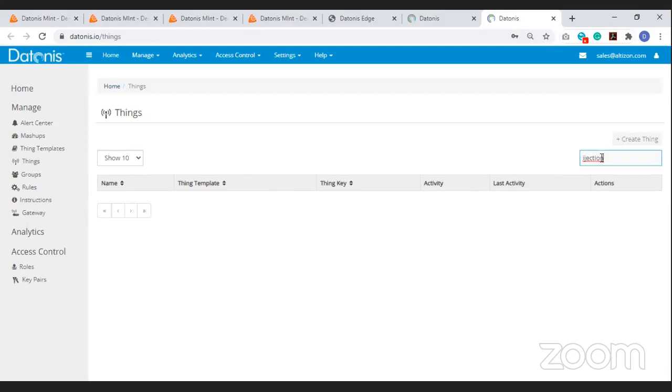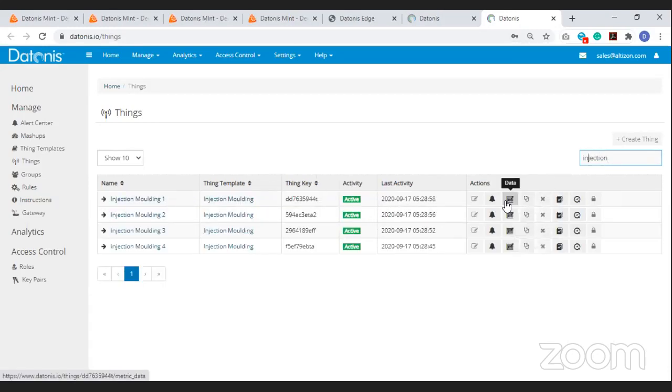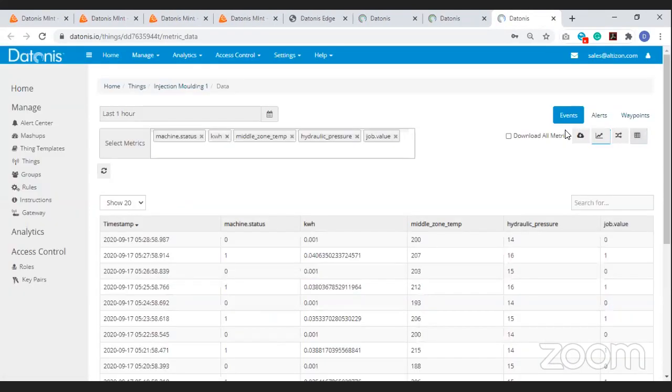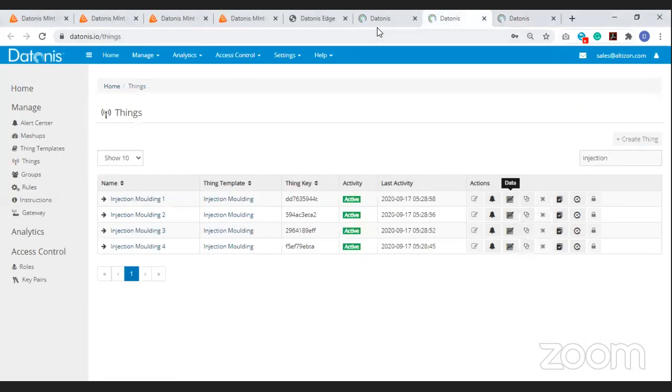If you already have a DCS, SCADA or a historian and there is an OPC DA availability there, we won't actually touch your process and go to the PLC level. In that case, we'll take the data from the OPC DA. So that is a different architecture that we can enable.